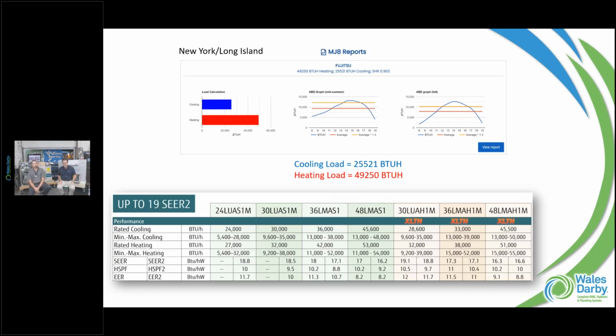Yeah, 100%. So I've been doing this analogy, and if it helps people - think about what you size for heating. The worst winter night, let's call it 5 degrees outside, and you want to maintain maybe 70 inside. So if you look at the spread between my hands, it's pretty wide. Now go to the other season - it's a 95 degree day, and you want to maintain maybe 70, 72. So you can see now that load is considerably smaller. But in that summer load, it's the factor of humidity - that's the largest part of the comfort side we want to achieve.